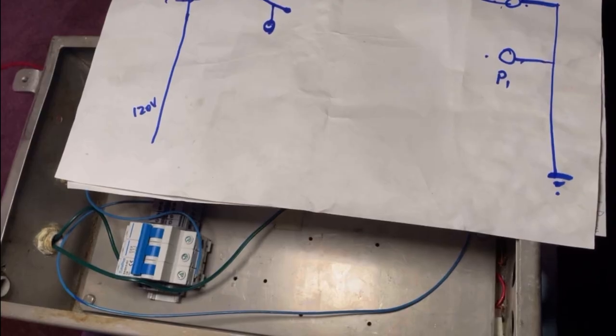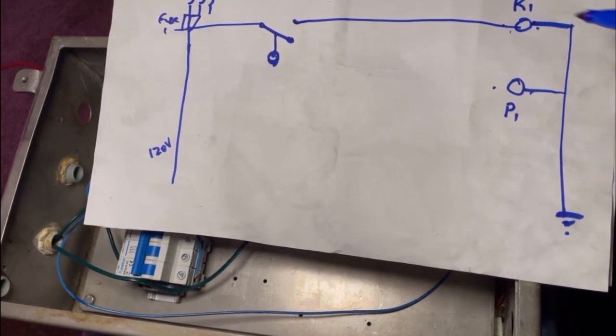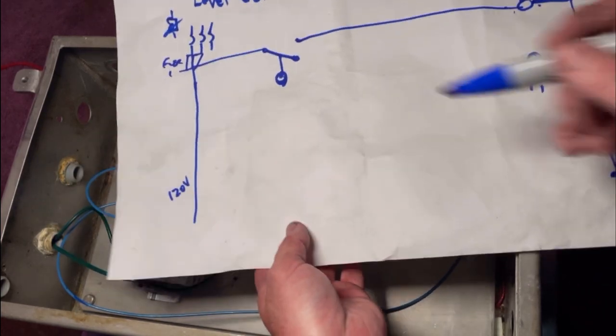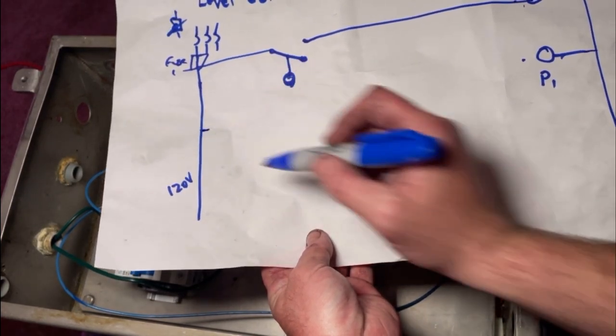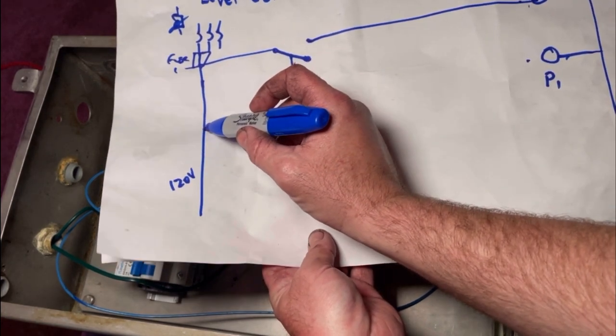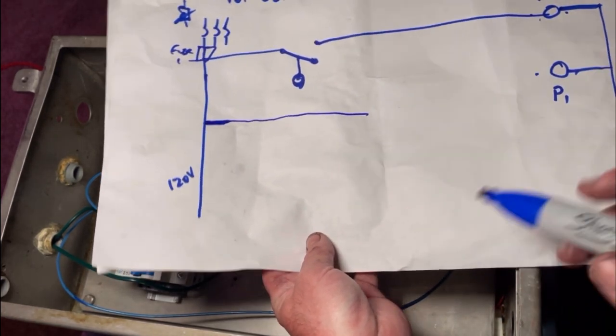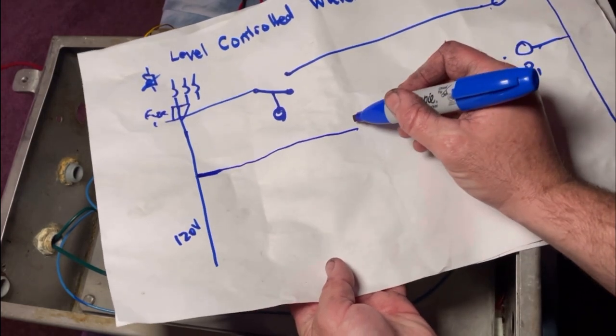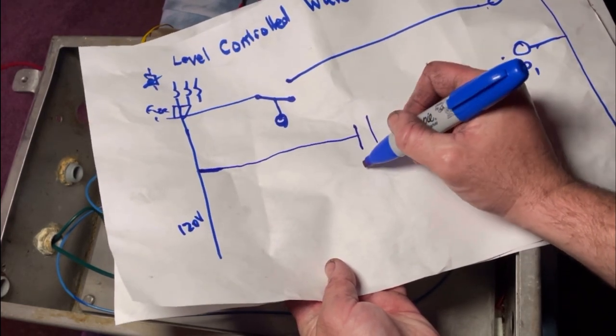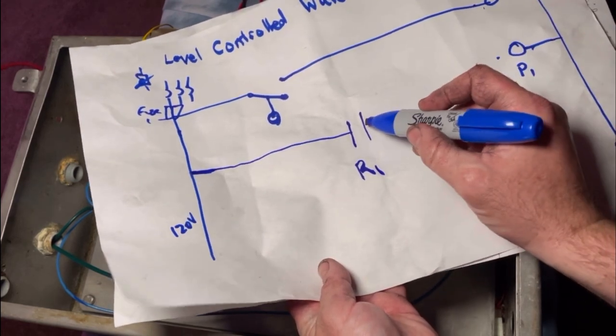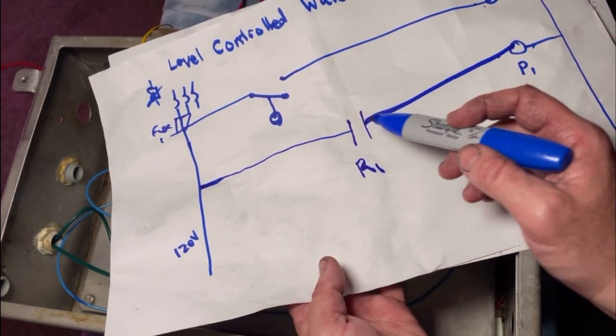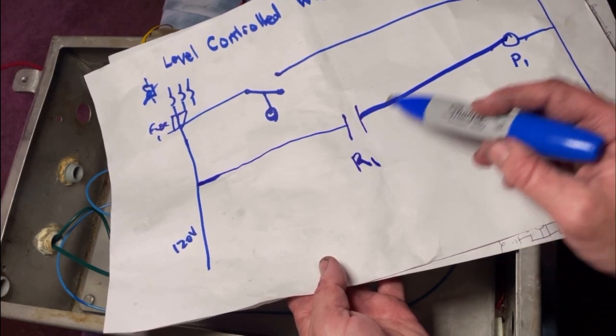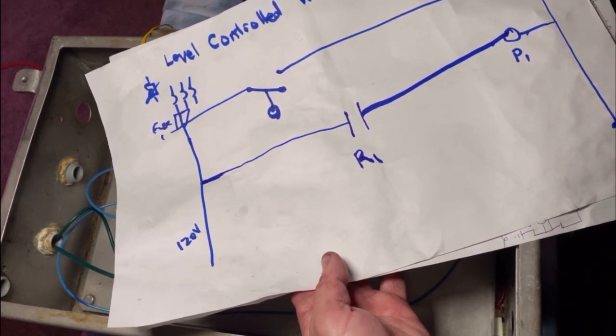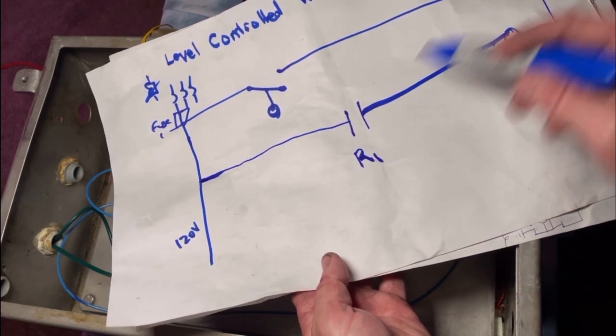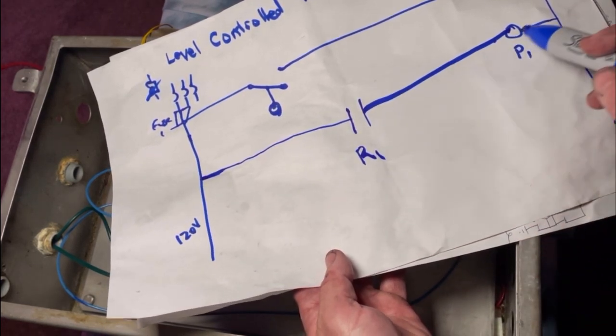Next. So I want to run pump 1. I want to run the power through one of the contacts in relay 1. So what I'm going to do is, I'm going to steal power from over here. I'm going to pull it from a point that's always hot. And then I'm going to run through one of the normally open contacts on relay 1. And I'm going to power the pump that way. So out normal state open. So out of the box, when relay 1 is not energized, there's going to be nothing here. When you turn on relay 1, that 120 is going to pass through there to pump 1.